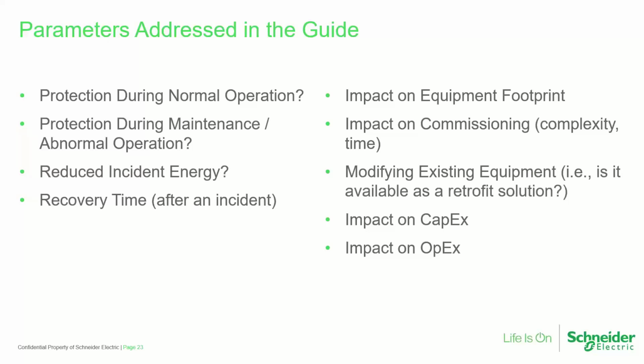Okay, thanks, Jeff. In this remaining part, we may breeze through a couple of things. I want to make sure that we do have plenty of time for Q&A. But you saw a preview of the guide that we've been working on putting together. Some of the parameters: are we getting protection during normal operation, such as opening or closing of a circuit breaker or switch? Are we getting protection during maintenance or abnormal operation? The answer to that can vary, and so we try to assess that to some extent.